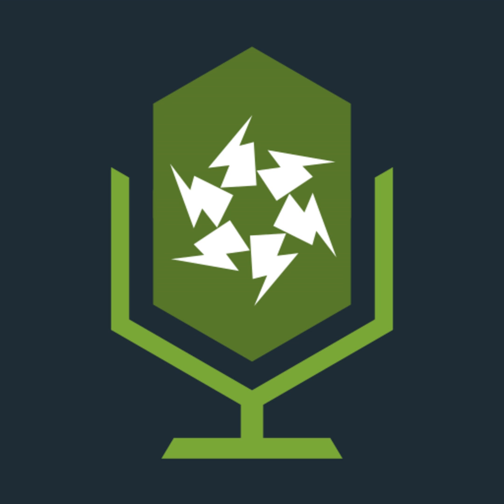So here we have an industry with another building. There's mains power. We've got a sub-main here. And we have our extraneous conductive parts coming into the building. And this is obviously the utility supply pipe, which cannot be used as an earth electrode. And so a separate earth electrode would have to be used. We cannot use the water utility supply pipe.